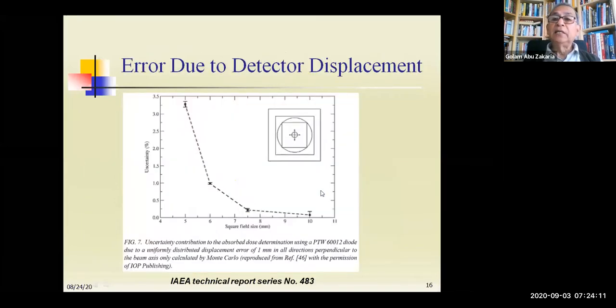So here is another important aspect. You see the displacement. When you have, for example, a square field of 5 millimeter, and you have some displacement in measurement of 1 millimeter, then you still have a mistake of 3%. So the placement of the dosimeter and its orientation is very, very important, and you should exercise so that you can place the dosimeter in the right position where you want to measure.